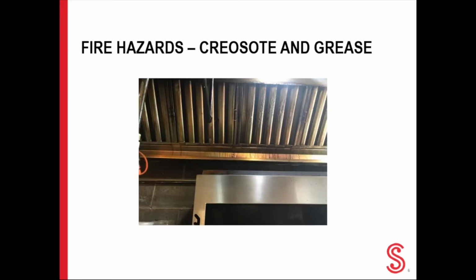The main hazard when cooking with solid fuel is creosote. So what is creosote? Creosote is made up of condensed volatile gases created in incomplete combustion of wood. Wood smoke mixes with water vapor from the cooking and forms creosote. Creosote clings to the interior of the cooking appliances and the exhaust system ductwork. Creosote is highly combustible and is well known for its fire threat in the chimneys of wood-burning fireplaces. So if you've ever been around a wood-burning fireplace, you may already know what creosote is.